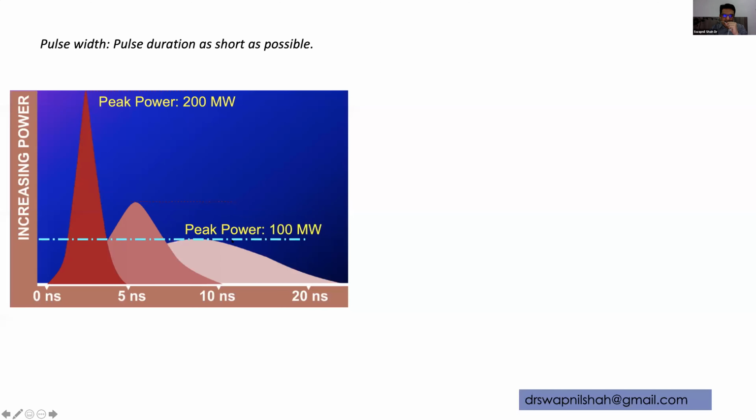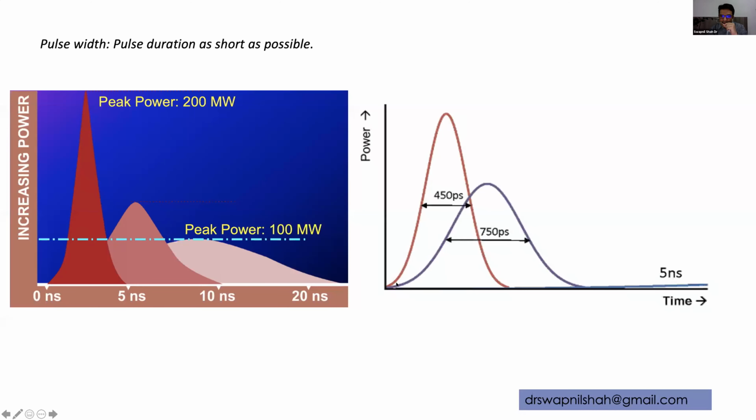So to compare with nanosecond laser, now if you see, this is a typical graph shown in Q switch lasers. And we know that with 20 nanoseconds, any machine can go up to say 100 megawatt, and reducing it to just 10 nanoseconds gets around 150, and 5 nanoseconds gets 200 megawatt. As compared to that, when you reduce the pulse width to picosecond laser, you get a peak power of the laser in the gigawatts range, not in the megawatt range. And if you comparatively see the difference between the peak power achieved by a nanosecond laser, this is a 5 nanosecond laser, as against a picosecond laser, the peak power is very, very high. And that's why these are very powerful but safe systems.